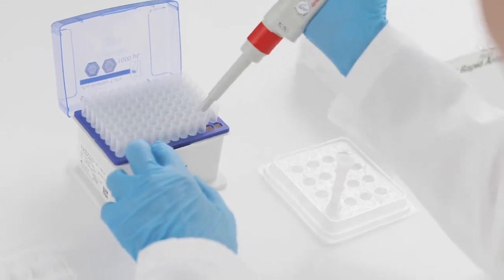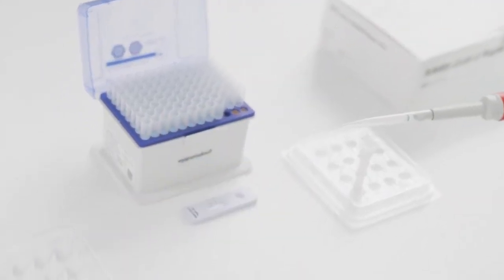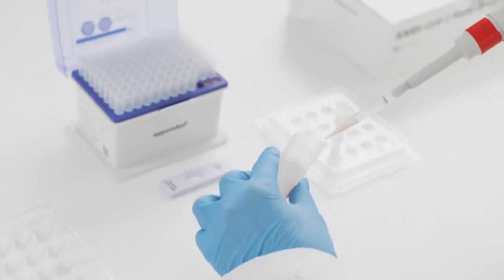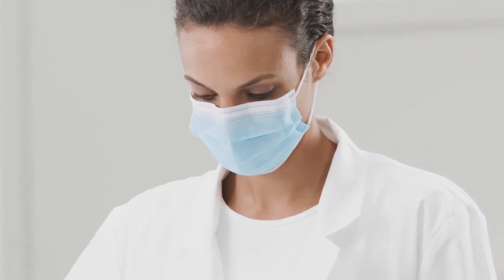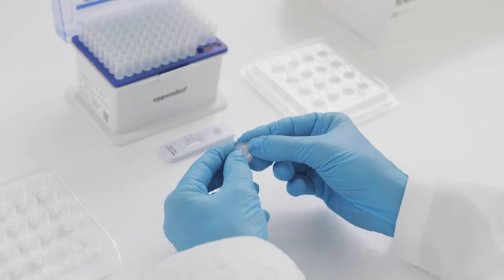If you want to prepare a sample from a viral transport media, use a micropipette to collect 350 microliters of the sample from the collection cup or viral transport medium and mix the sample with the extraction buffer. Afterwards, press the nozzle cap tightly onto the tube.